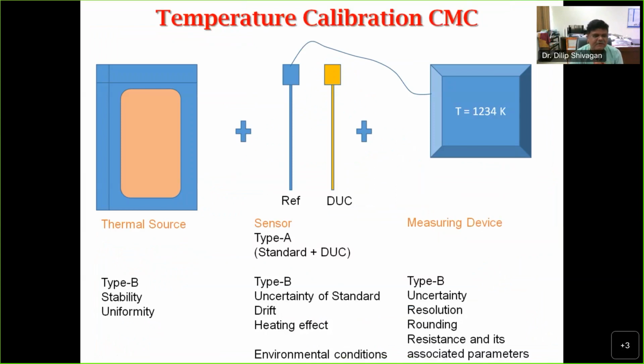Okay, so what essentially we need for thermal measurements is one thermal source, which is absolutely very stable, then sensors, one as a reference and another DUC that you want to measure, and both will be attached to some measurement device which should be very highly stable, and should be characterized by the electrical metrology people. So with these, there are uncertainties associated with, say, the source. They are mostly type B in nature: stability and uniformity. Because of the sensor, we have the reported standard uncertainty, and we have the drift. For a platinum resistance thermometer, because it is not a standalone thermometer, we need to give a current to measure the resistance. This current will have I squared joule heating, so those components are also important. And environmental conditions, if we are using the read heads, and if they are affecting.